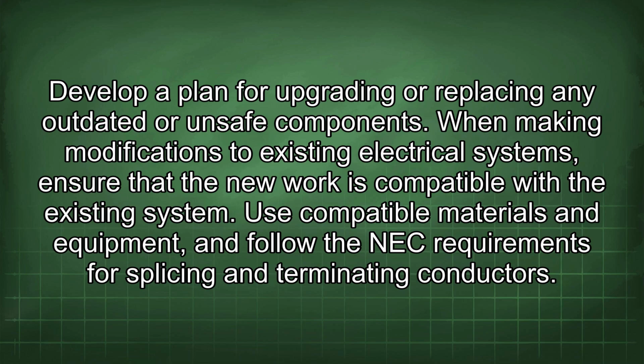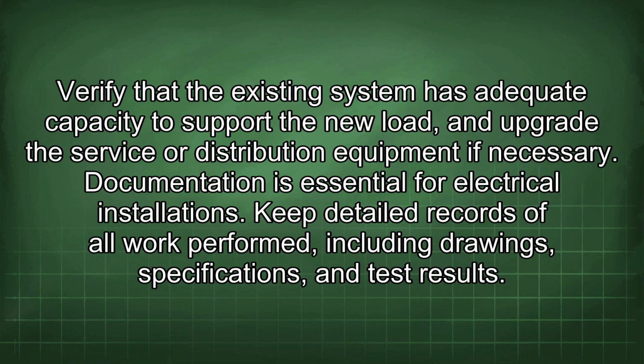When making modifications to existing electrical systems, ensure that the new work is compatible with the existing system. Use compatible materials and equipment, and follow the NEC requirements for splicing and terminating conductors. Verify that the existing system has adequate capacity to support the new load, and upgrade the service or distribution equipment if necessary. Documentation is essential for electrical installations.